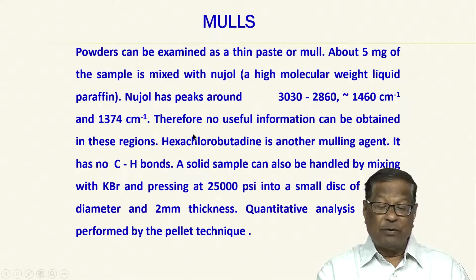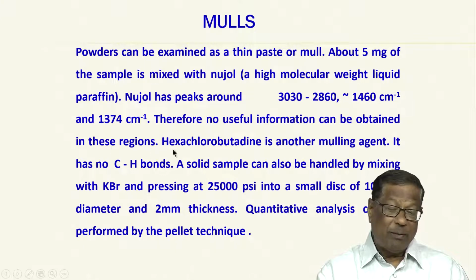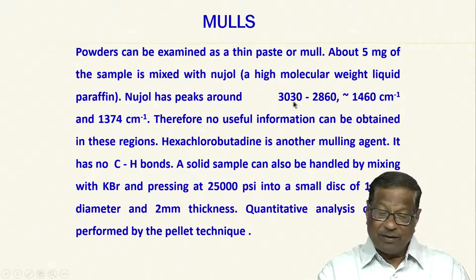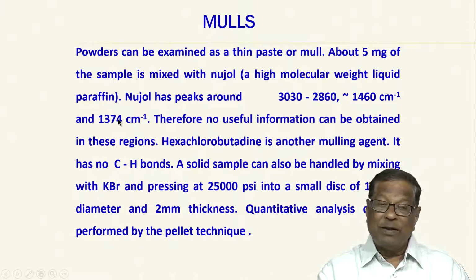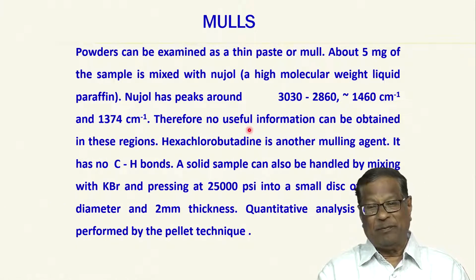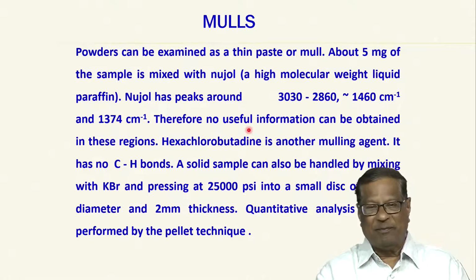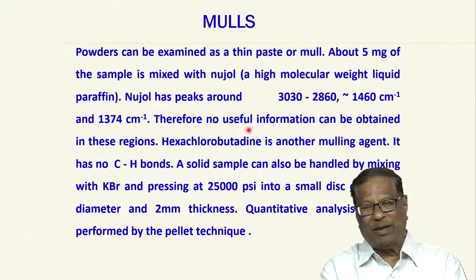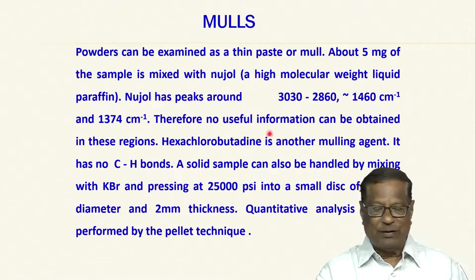I will show you some of the IR peaks using Nujol. Actually, no useful information can be obtained in these regions, okay, 2860, 1462, 1374. You will not get any special information because Nujol itself has peaks which are quite strong. So, any IR peak that is available in that range gets masked, it gets submerged in the Nujol peak. So, if you are interested in those regions, better avoid Nujol.